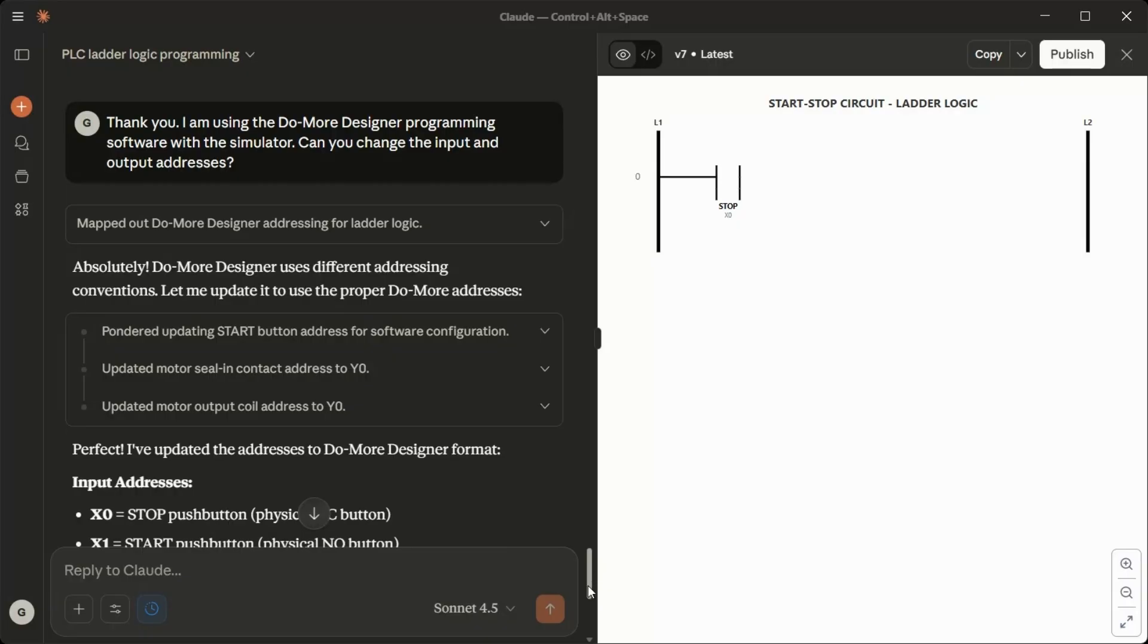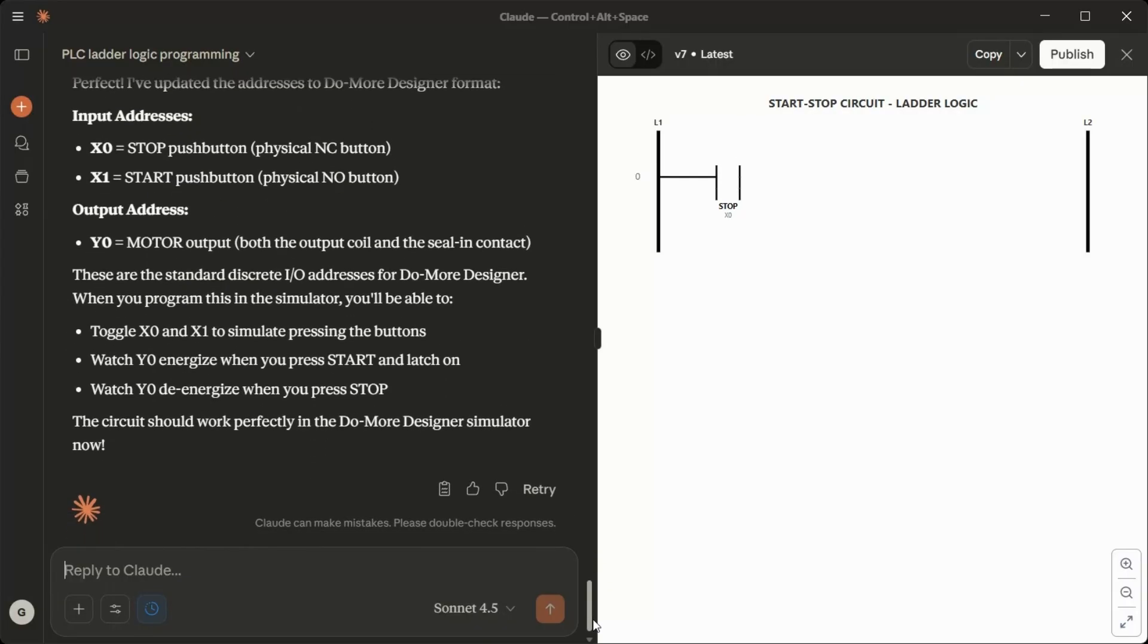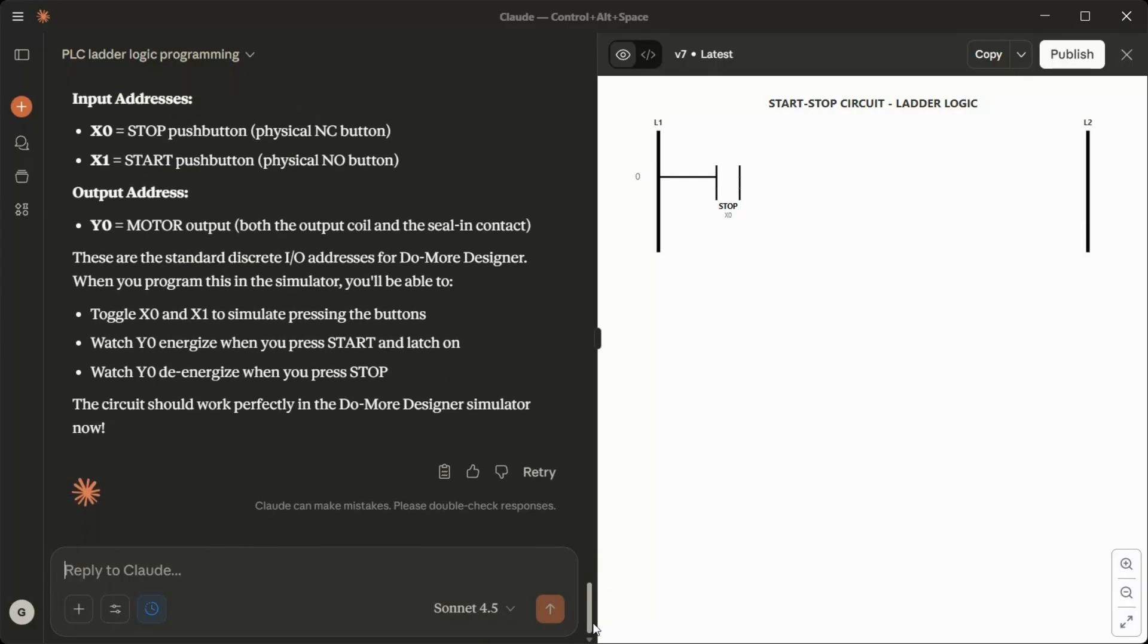These are the standard discrete IO addresses for Do More Designer. When you program this in the simulator, you'll be able to toggle X0 and X1 to simulate pressing the buttons. Watch Y0 energize when you press start and latch on. Watch Y0 de-energize when you press stop. The circuit should work perfectly in the Do More Designer simulator now.